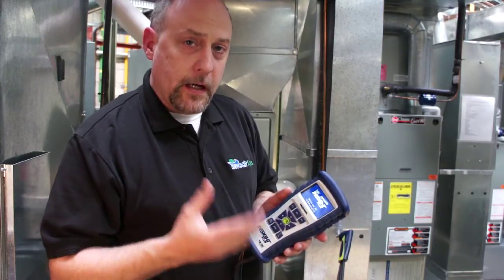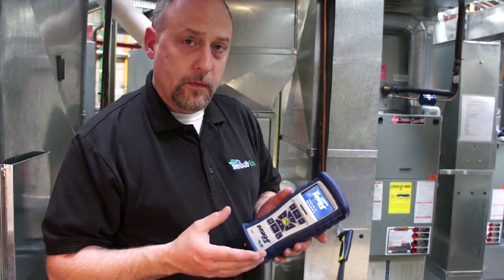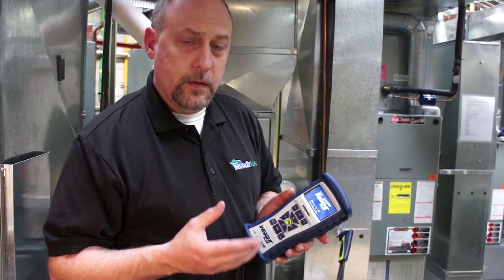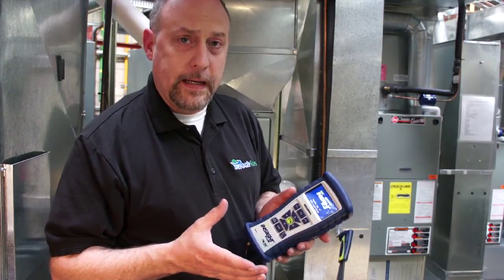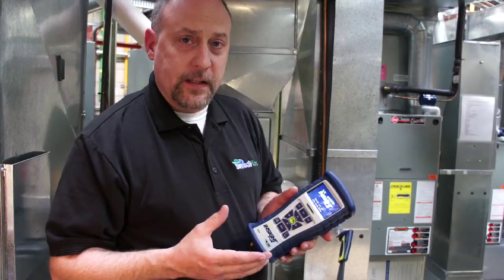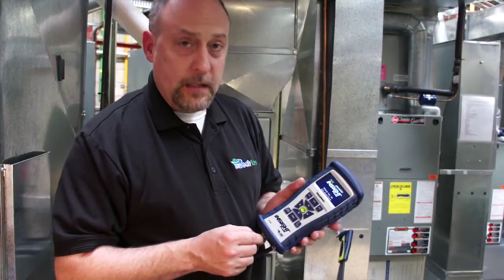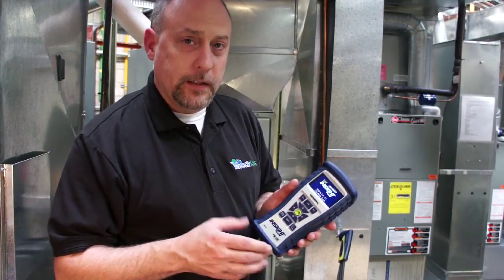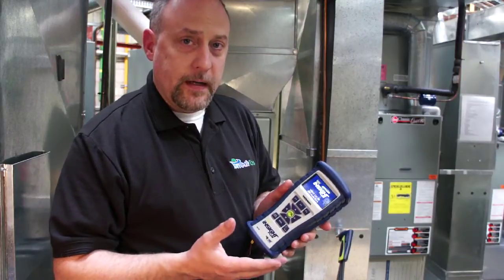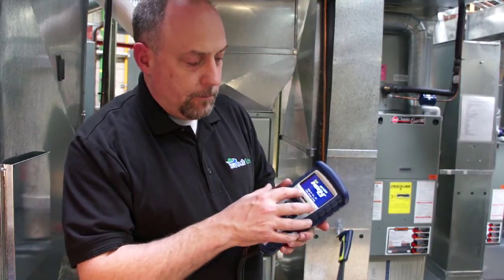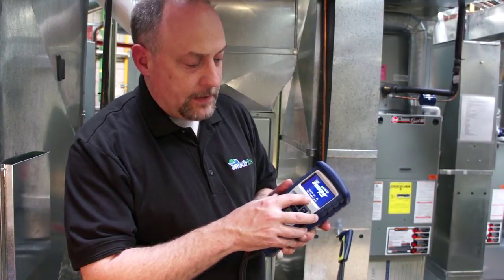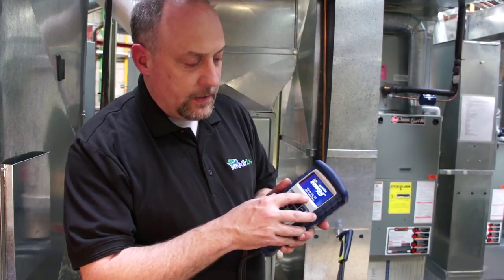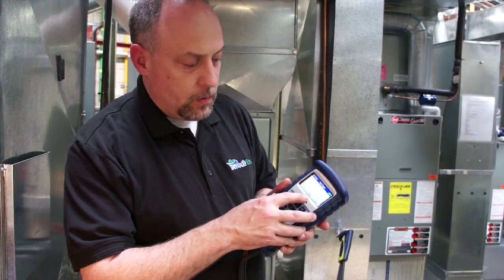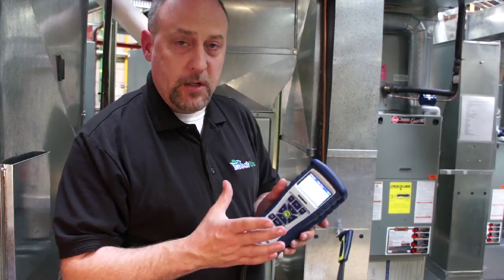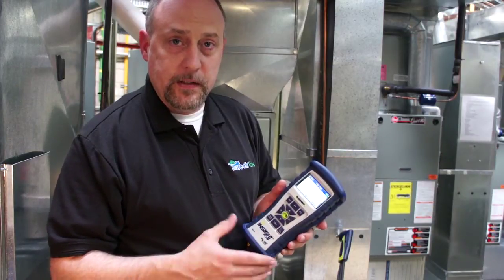It's going to give it enough time to zero out the O2 to fresh air, so it'll take it to 20.9 and purge any gas out of the CO cell. It's going to go out and check, make sure there's a stack thermocouple plugged into this, and once it goes through that initial configuration, it'll pop out of here, so it should pop out about any time now, and we'll see it go into the warm-up mode. So 2, 1, 0, and now we're into the measurement mode, and we can start a combustion test.